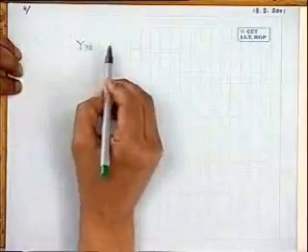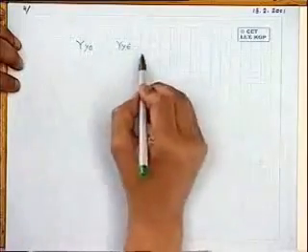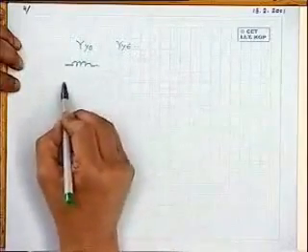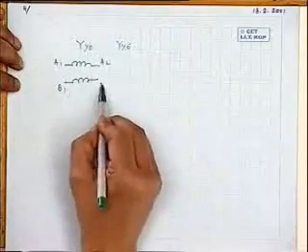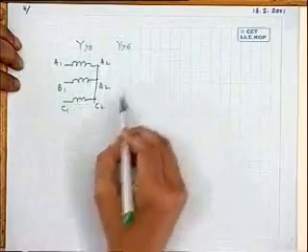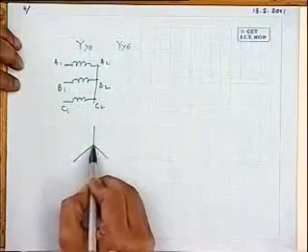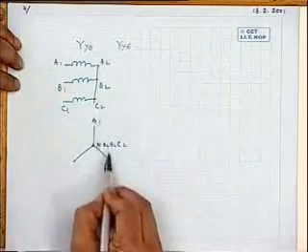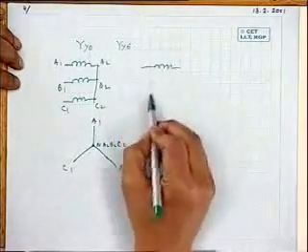I will now tell you, for example, for star-star connection, what are the two connections possible? YY0 is possible and YY6 is possible. This I will just very quickly draw because I have already told this, but not in this form. So once again, suppose this is A1, A2, B1, B2, C1, C2, and you have shorted it. This is the primary voltage, common neutral, A2, B2, C2. And these are your primary voltages B1, C1.